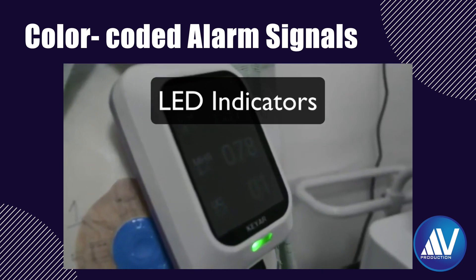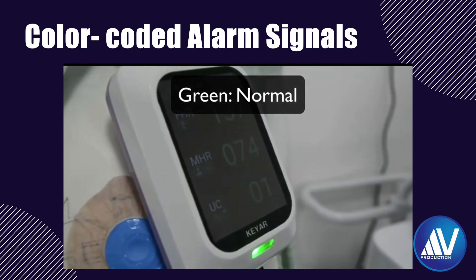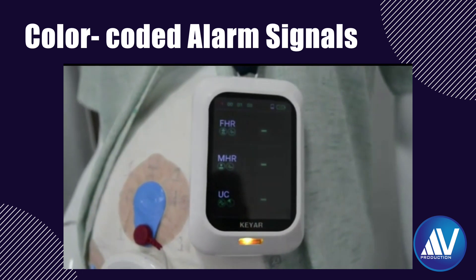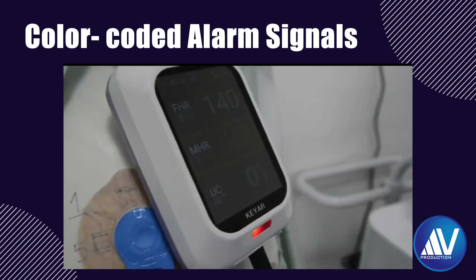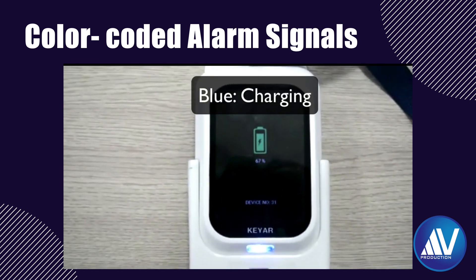One feature I like is the color-coded alarm signals emitted by the KEYAR device. If the LED shows green with uniform beeps, it means the condition of the fetus and mother is normal. Orange color means there is a disconnection — you will have to reconnect the device. Red color with a high-pitched beeping sound indicates a critical condition, i.e., fetal or maternal tachycardia or bradycardia — the staff should immediately inform the obstetrician. Blue light indicates the device is being charged, which comes on when placed in the charging dock.